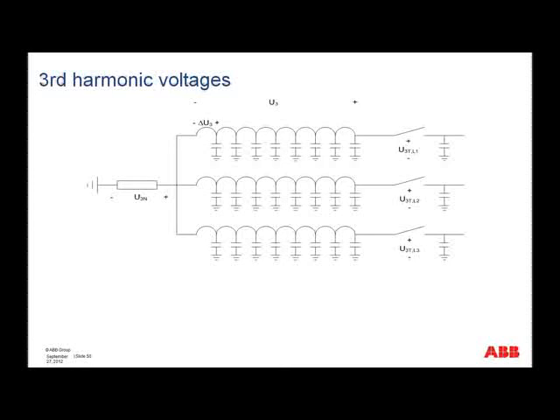Now you can see that whether or not there's a generator breaker then can make some difference. If there's no generator breaker, then this capacitive coupling doesn't change, okay, because it's not possible for that point to be open. But if the generator circuit breaker is there, then the capacitive coupling differs between operating conditions. Now, mostly it would be closed under all normal operating conditions, but during standstill or during run-up, then it would be open.